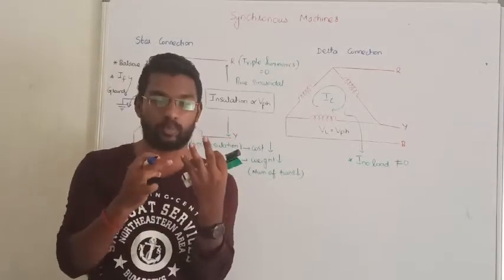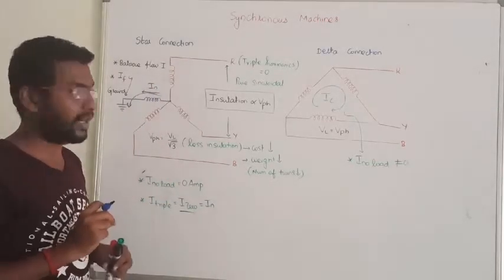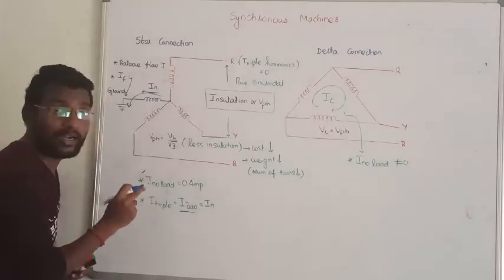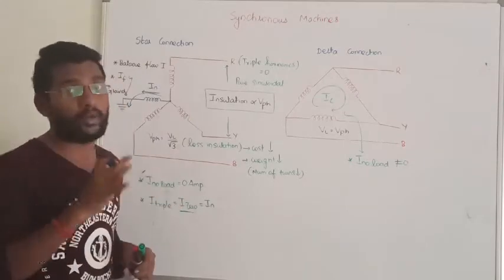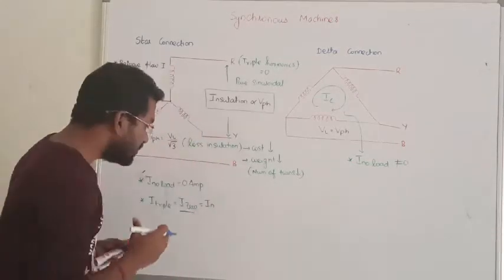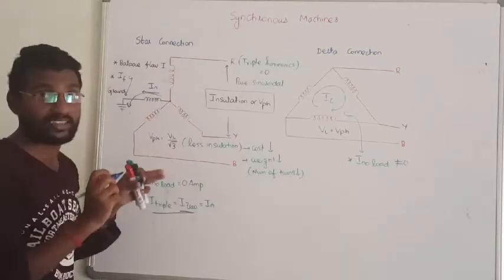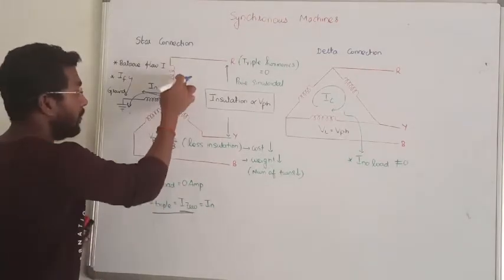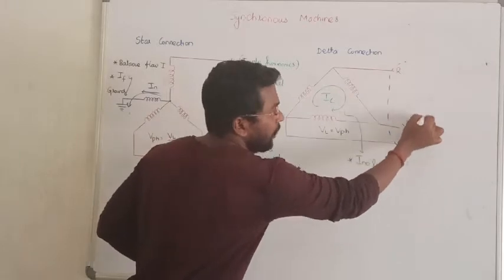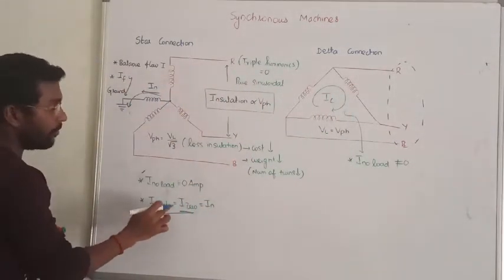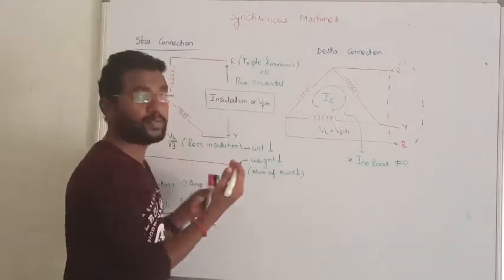If we look at the phase sequence — positive sequence, negative sequence, and zero sequence — the zero sequence component is present when the neutral line is present. In delta there is no neutral line. The zero sequence current, or triplen harmonic current, always circulates equally. In a star connected network, the triplen harmonics present will be diverted through the neutral line. But that is not possible in a delta connected network, where the triplen harmonics circulate internally. This is one more significant advantage of giving preference to a star connected network.